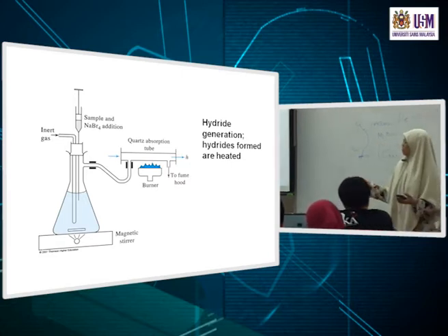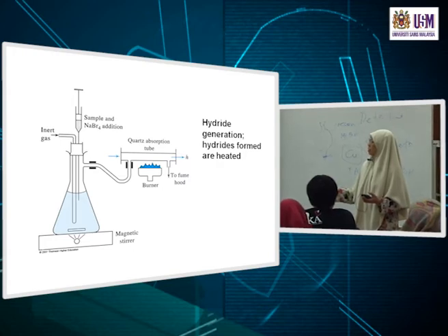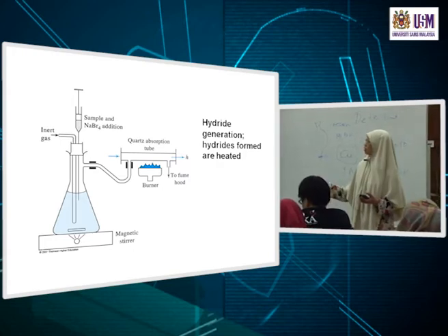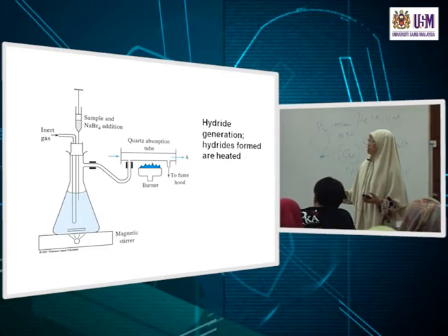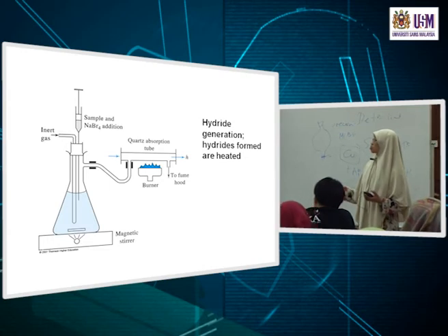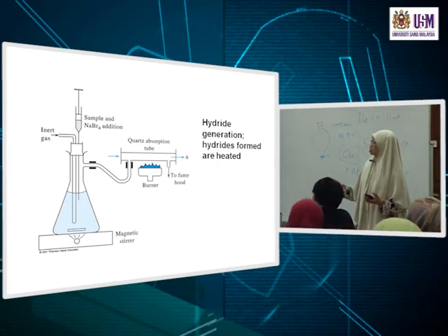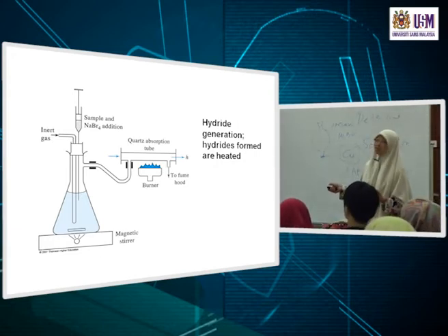Where we still have the flame, but we have a quartz tube, we have a reaction vessel on the side where you now add a reducing agent to your sample solution. Your sample solution does not go through a nebulizer and form aerosol. We don't go through that sample introduction method anymore. We now introduce the sample in a different way. So this is an accessory where the sample introduction technique is different.